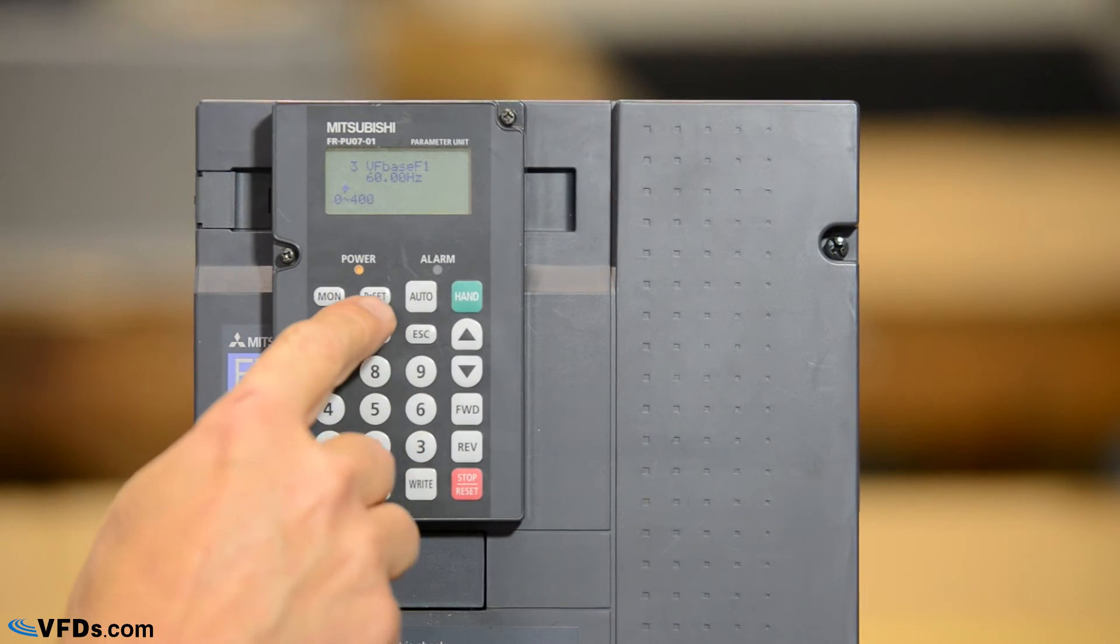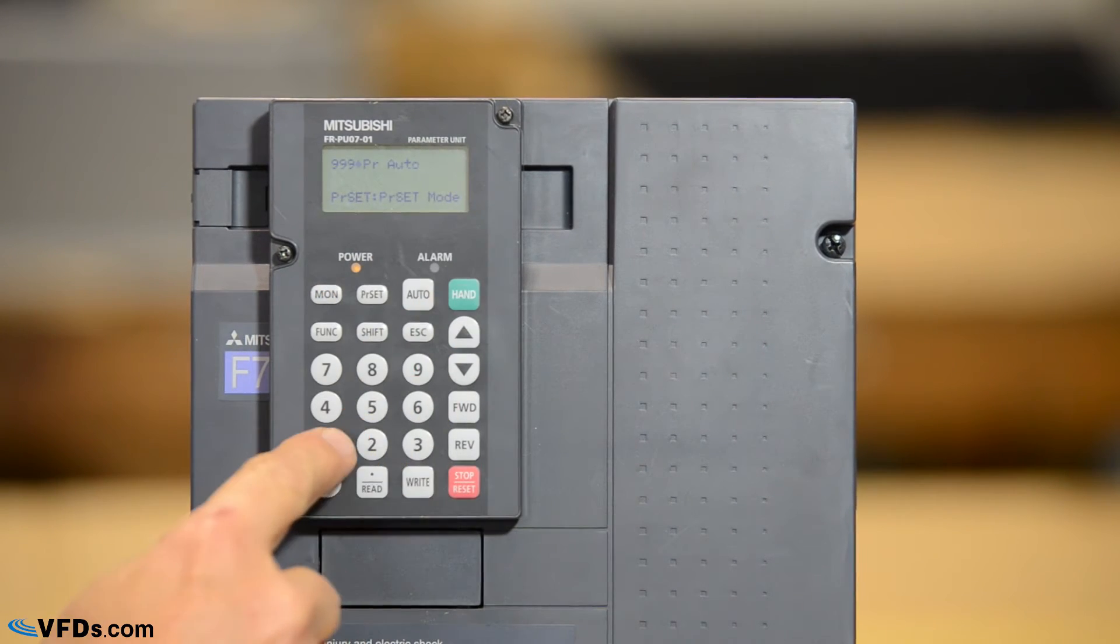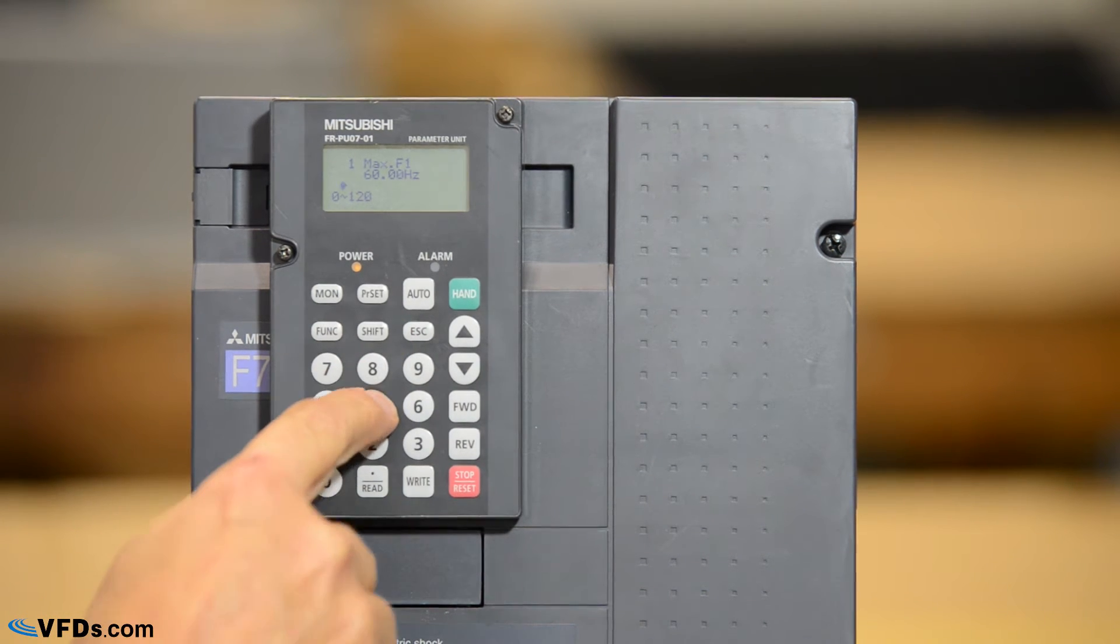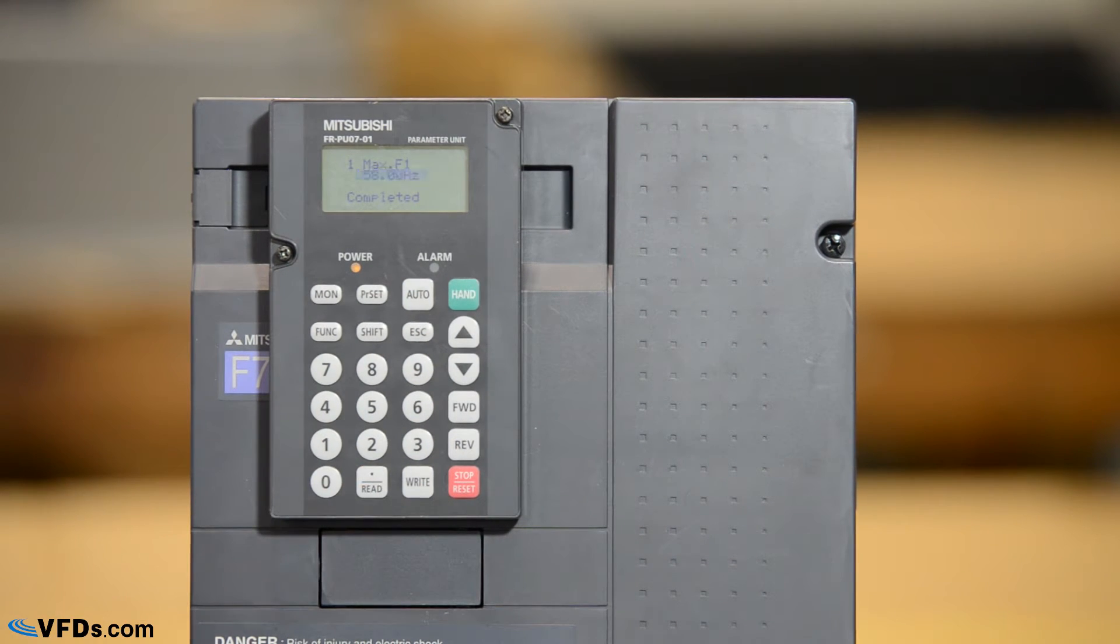Now let's cover the first 10 parameters which are the basic parameters that you're going to want to set. We hit parameter set 1 read. This is your maximum frequency. The maximum frequency is set at 60 hertz. Maybe I don't want my motor to go that fast so I'm going to change it to 58 hertz and push write. Now it will not allow the motor to go faster than 58 hertz.